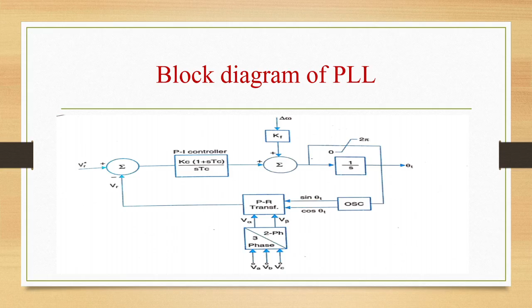Now let us see the control hierarchy and system control. Control hierarchy in a VSC based HVDC link is similar to that in an LCC based HVDC link, except for some major differences. For example, a VSC uses self-commutated devices such as IGBTs, and hence there is no problem of commutation failure caused by dips in the AC voltage. The DC voltage in a VSC based HVDC link is independent of variations in the system voltage, except under fault conditions.